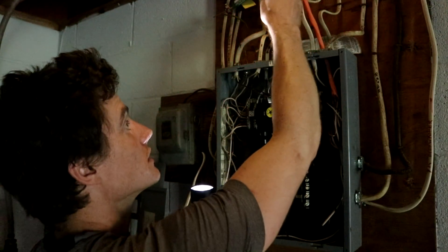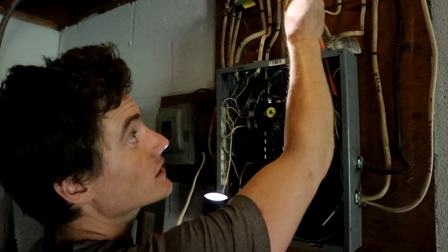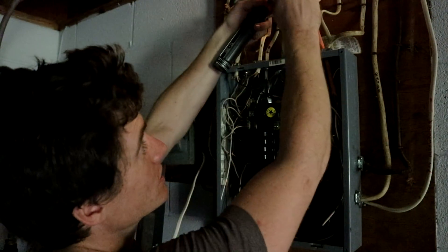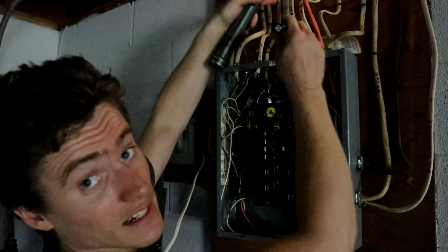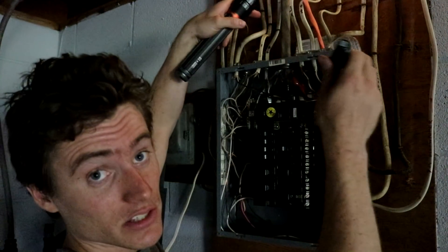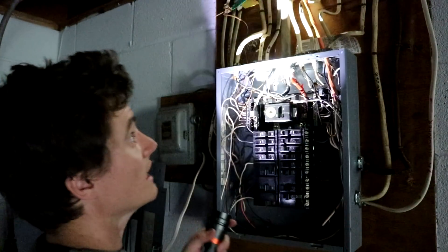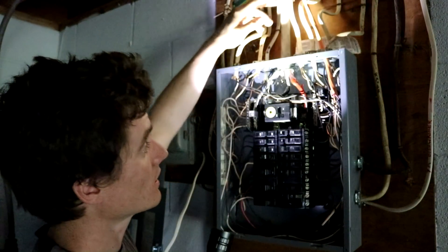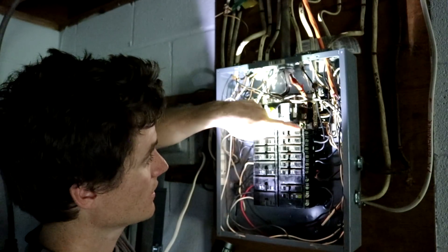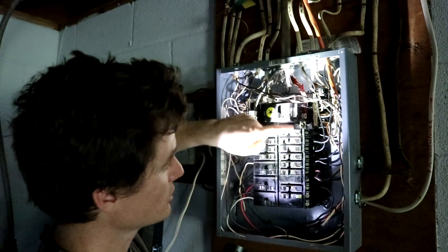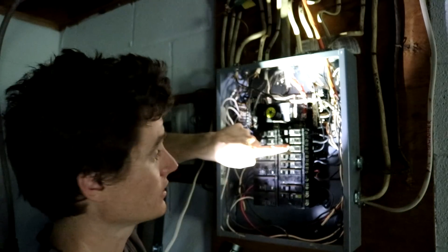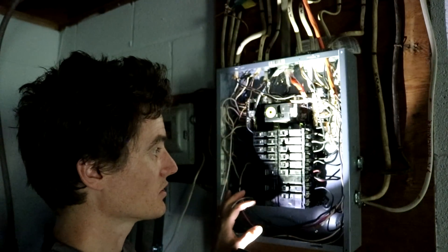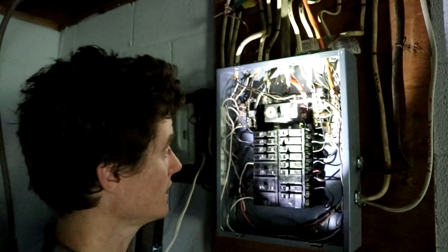Must be that one. Sometimes what I'll do though is I'll check the wires beside it because sometimes you'll have two wires right beside each other and you'll touch one wire, and just because it's close, you'll set that one off. But it's this. That wire had a number on it, 3R, meaning that it goes to the way they did it. It's 3R, which means it's the third breaker down on the right.